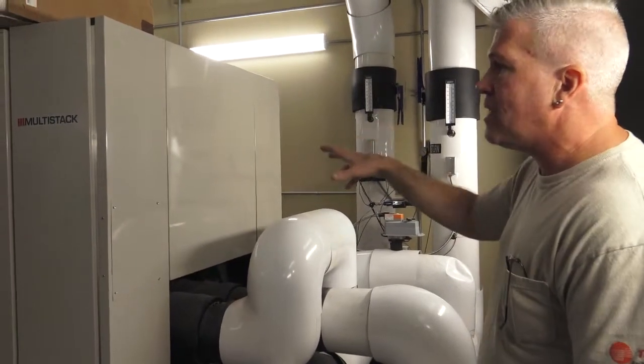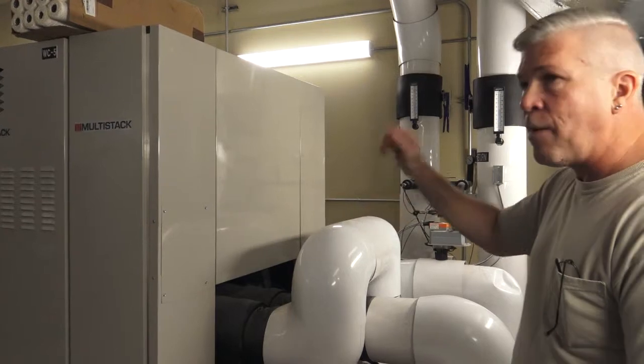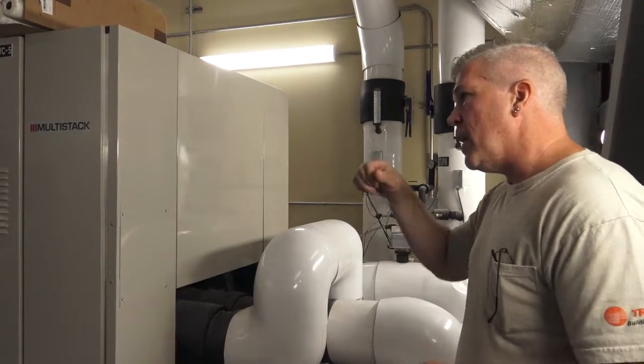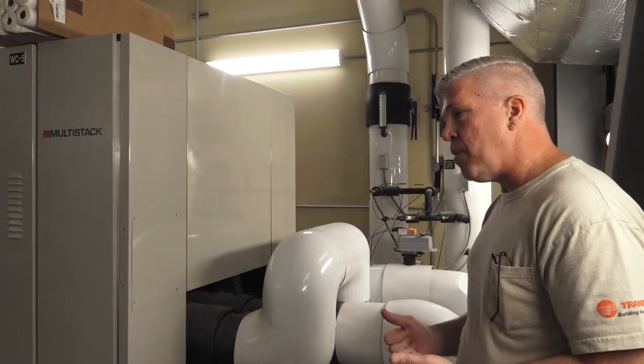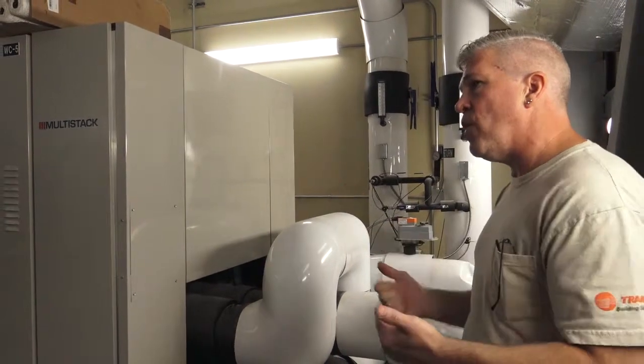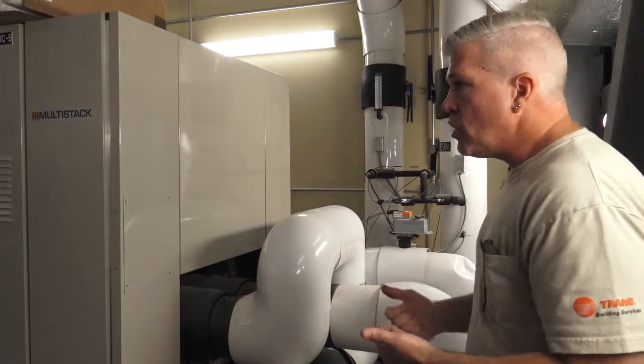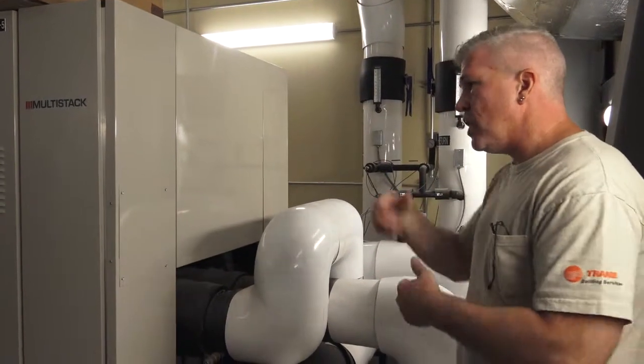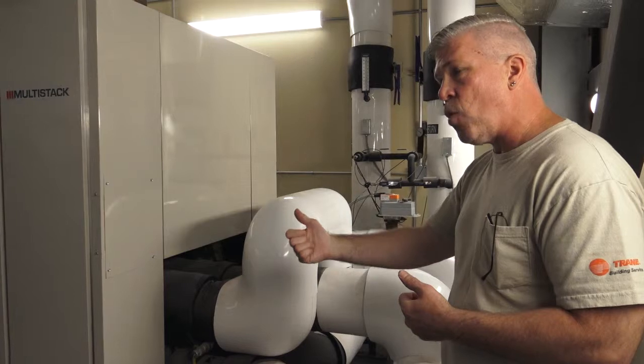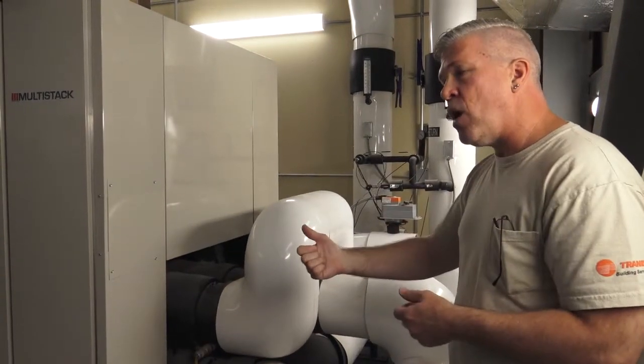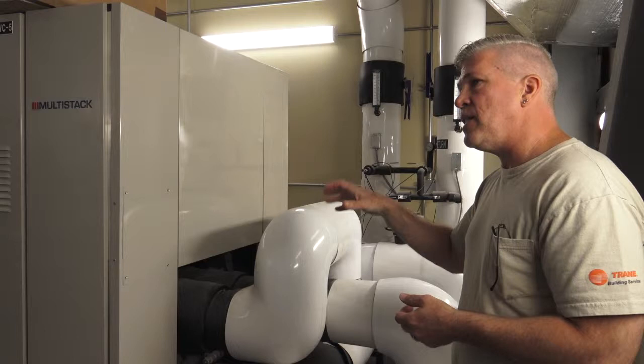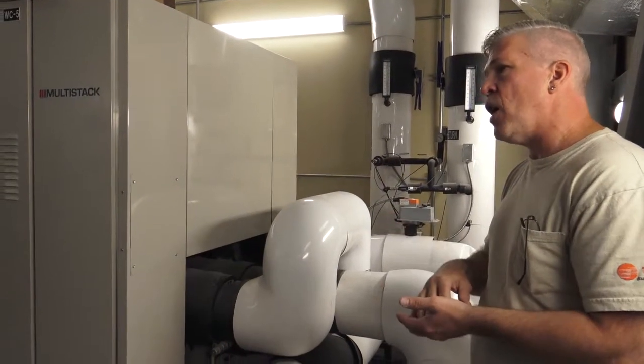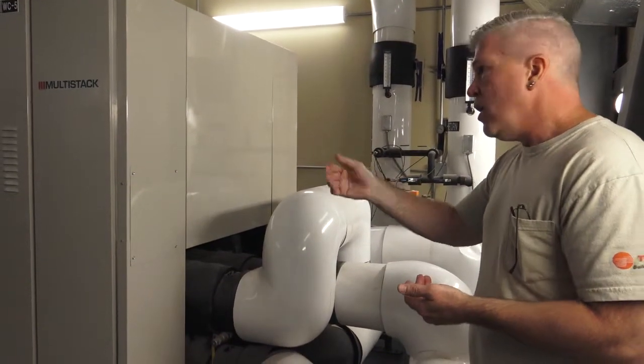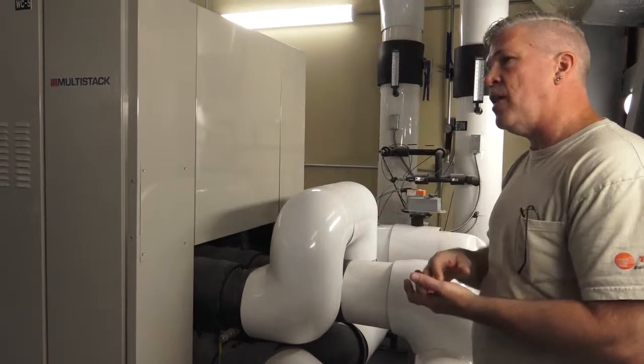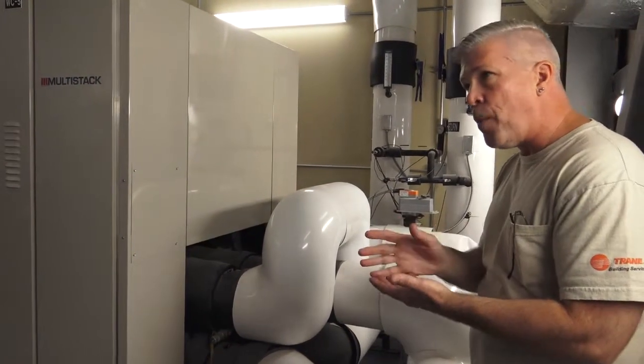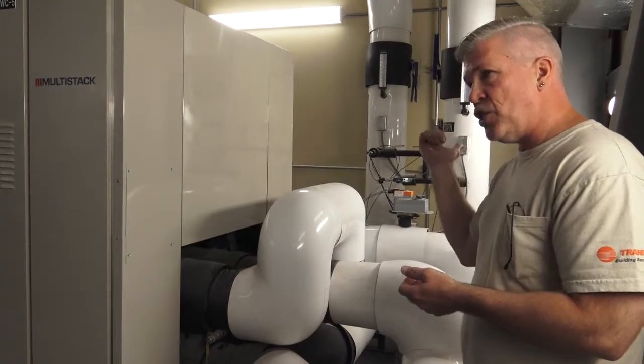The multi-stack itself is running in what they call a simultaneous mode. So it's looking to make chill water and hot water at the same time, but it bases it on whichever one of those has a higher demand. So if they have a high demand, like say this summer where you're looking to produce a lot of chill water, well, it's also creating hot water. The hot water that this supplies out is 120 degrees, so if it starts making water excessive to that 120, for each of the sections there's a bypass or mixing valve that'll start to open, and it'll start dumping water to the geofield.